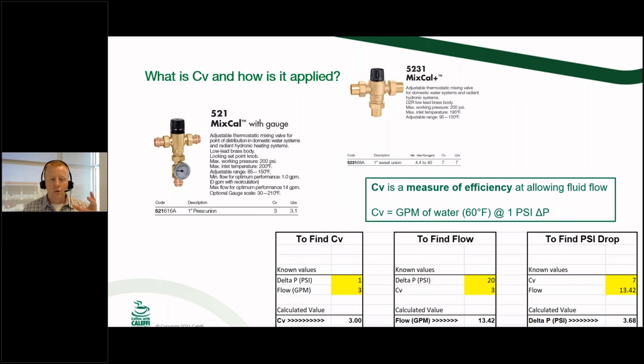When you look at that CV number, it's a coefficient, and it's going to tell you the gallons per minute of water that you're going to get at a 1 psi pressure drop through that valve. So you look at this little guy over here on the left, this 521 series mixing valve, it's going to have a CV of 3. That means you're going to have a 3 gallon per minute flow rate at a 1 psi pressure drop. Now, that does not mean that you can't go over 3 gallons per minute. It's just kind of a benchmark. It's a quick, easy way to look at 2 different valves and say, this one has 3 and this one has 7, and this one can obviously flow more with less pressure drop than this one.